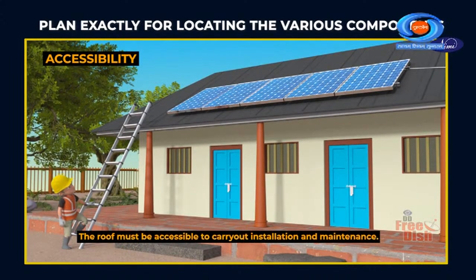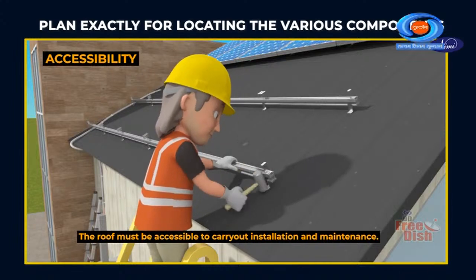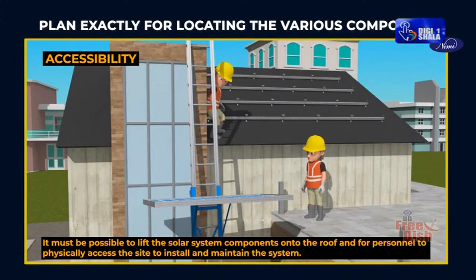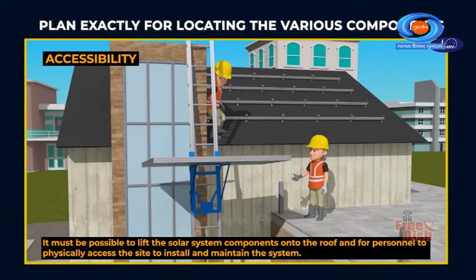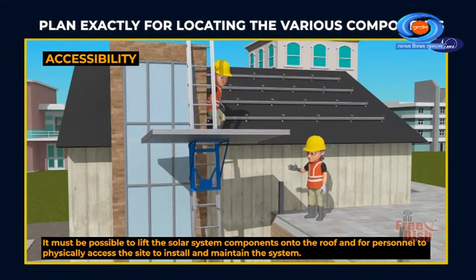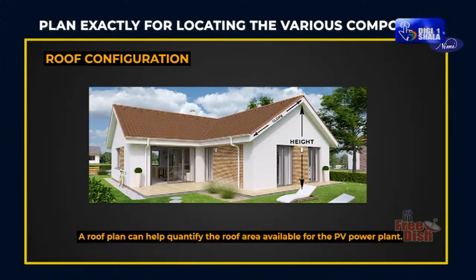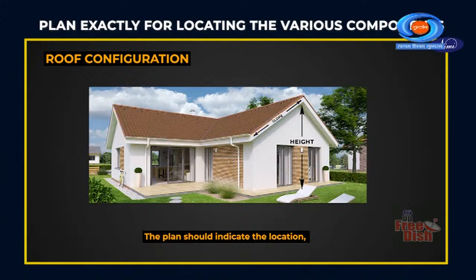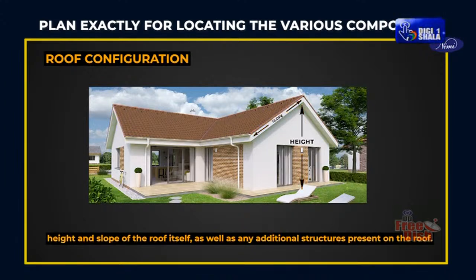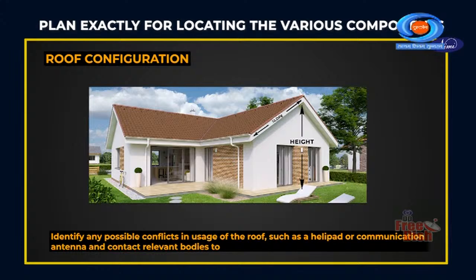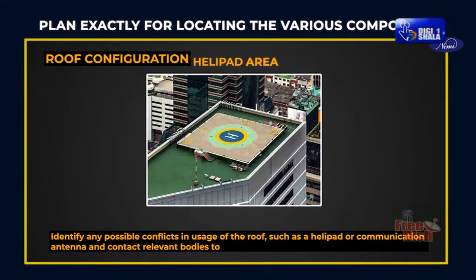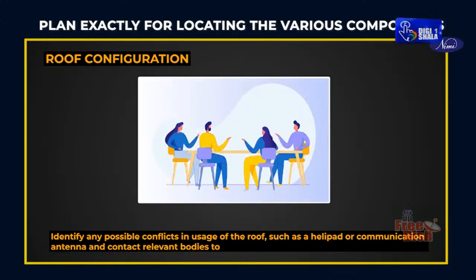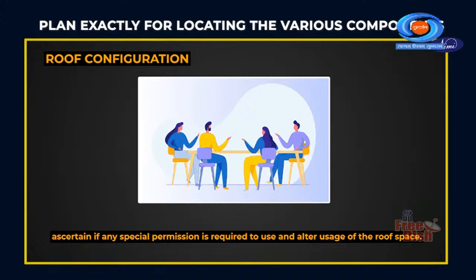Accessibility. The roof must be accessible to carry out installation and maintenance. It must be possible to lift the solar system components onto the roof and for personnel to physically access the site to install and maintain the system. Roof configuration. A roof plan can help quantify the roof area available for the PV power plant. The plan should indicate the location, height and slope of the roof itself as well as any additional structures present on the roof. Identify any possible conflicts in use of the roof such as a helipad or communication antenna and contact relevant bodies to ascertain if any special permissions are required to use and alter use of the roof space.